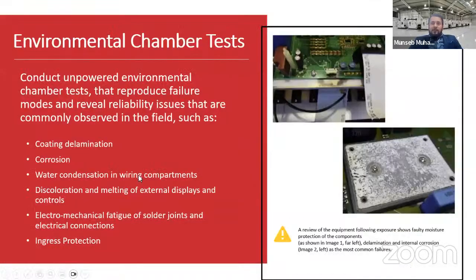It will tell you a lot about the coating delamination issues, the corrosion issues, the water condensation in the wiring compartments, the discoloration and the melting of external displays and controls, electromechanical fatigue of the solder joints and electrical connections, and the ingress protection of the inverter itself. Here you see pictorial evidence of a very healthy inverter once it was exposed to environmental test. You could see it's developing moisture issues within the components and the PCBs.